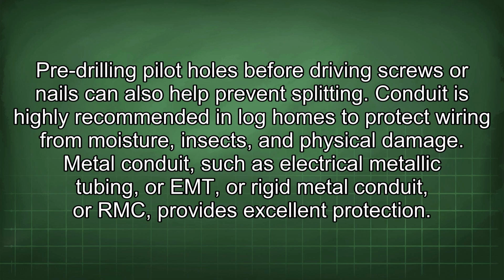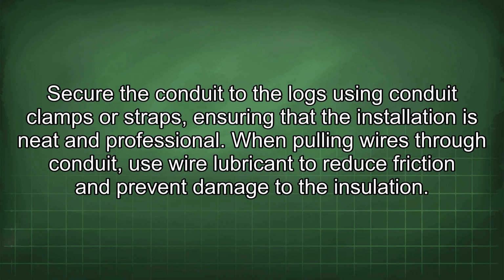Conduit is highly recommended in log homes to protect wiring from moisture, insects, and physical damage. Metal conduit, such as electrical metallic tubing, or EMT, or rigid metal conduit, or RMC, provides excellent protection. Secure the conduit to the logs using conduit clamps or straps, ensuring that the installation is neat and professional. When pulling wires through conduit, use wire lubricant to reduce friction and prevent damage to the insulation.